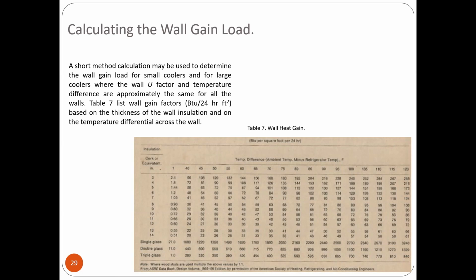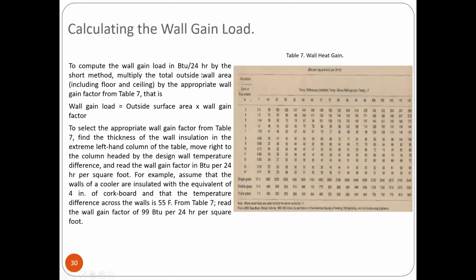So, table 7 lists wall gain factors, BTU per 24 hours per square foot, based on the thickness of the wall insulation and on the temperature differential across the wall. So, this is now the cork or equivalent insulation, temperature difference. Yan. So, kukuha mo yung value. Wall heat sa wall per square foot of the wall. Okay, ito naman yung mga glass. To compute the wall gain load in BTU per 24 hours by the short method, multiply the total outside wall area, including floor and ceiling, by the appropriate wall gain factor from table 7. So, wall gain load is outside surface area times wall gain factor.